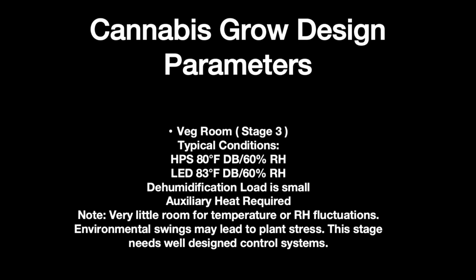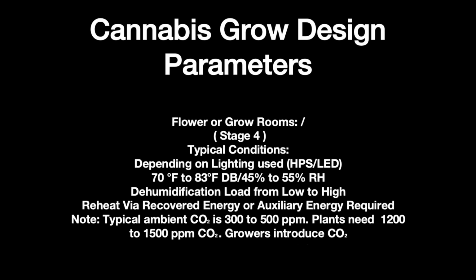One of the things that's interesting about the veg rooms is that the plants are very susceptible to fluctuations in temperature and relative humidity. One of the first projects we did, they were using typical commercial HVAC equipment in there, and they were seeing substantial swings in temperature and humidity. And what the grower told us was that once they took them out of the veg room and put them into the flower rooms, it took a couple of weeks for those plants to readjust because they had been stressed so heavily in the veg room. So temperature and humidity control in the veg rooms are extremely critical, but it's critical in all of these rooms.